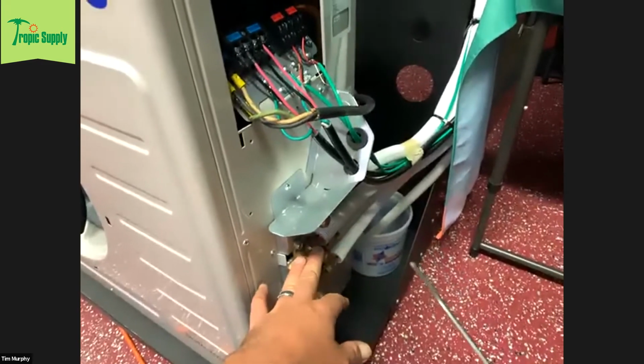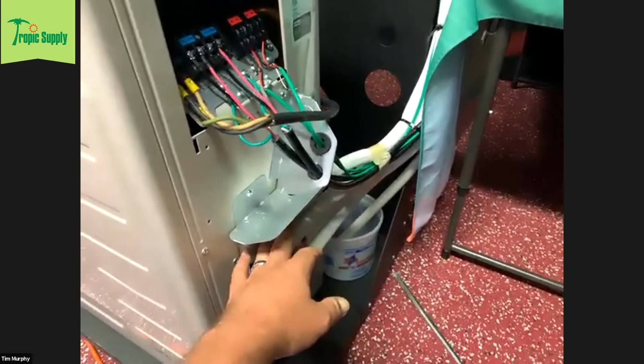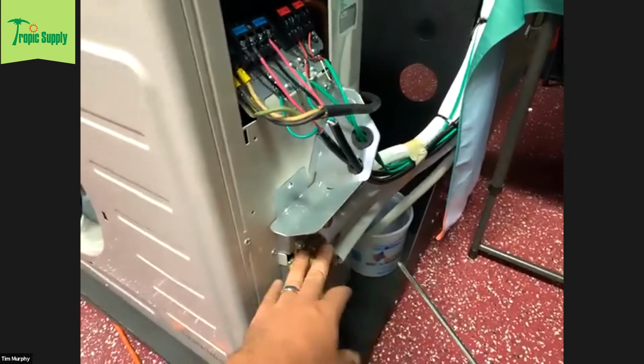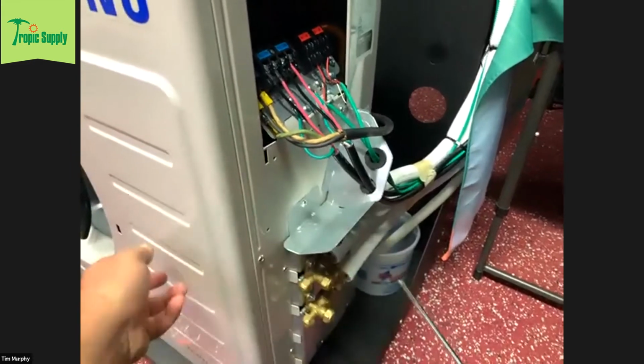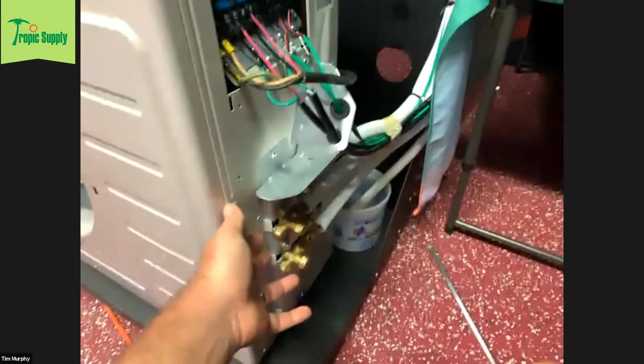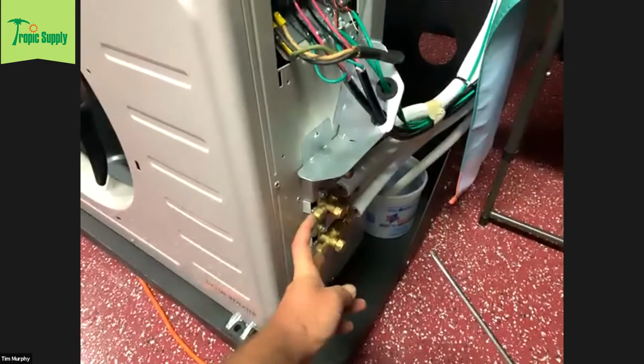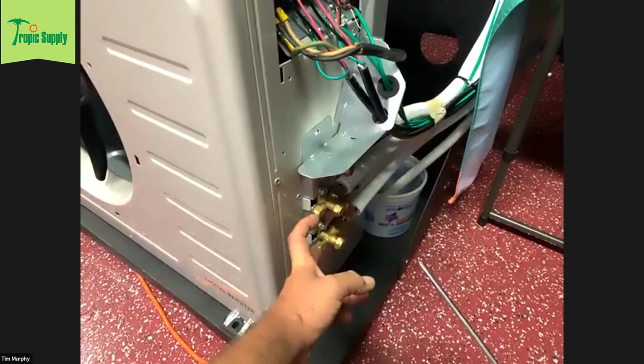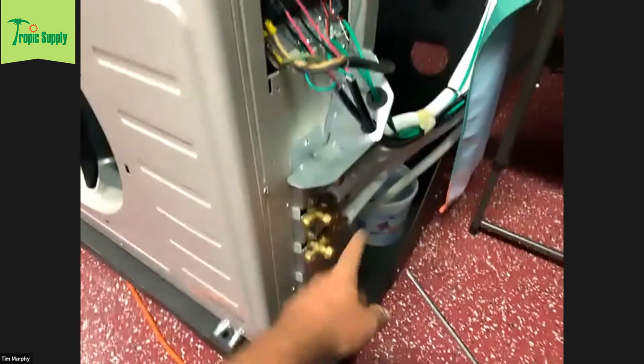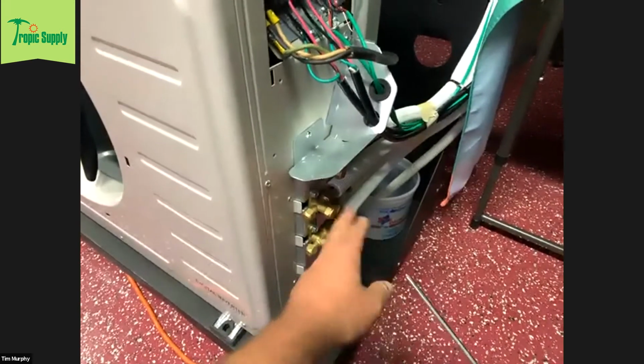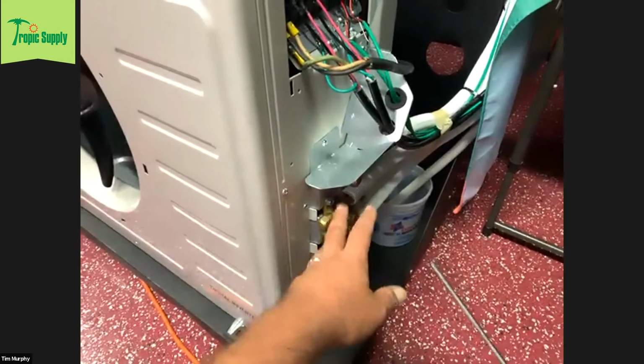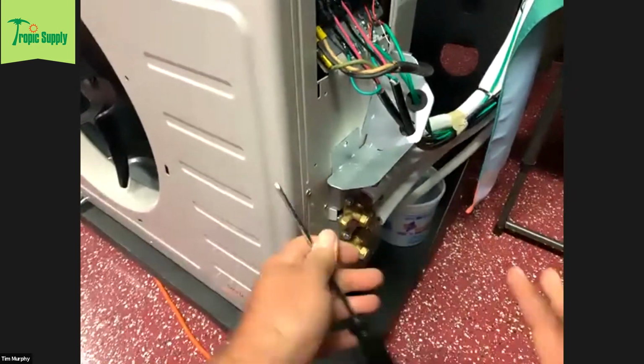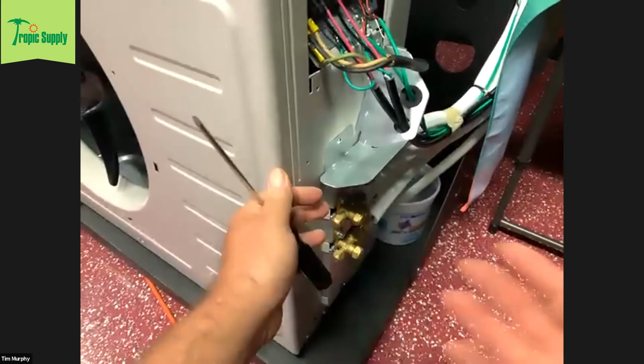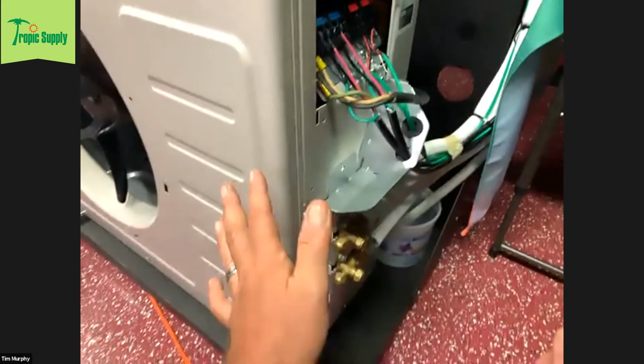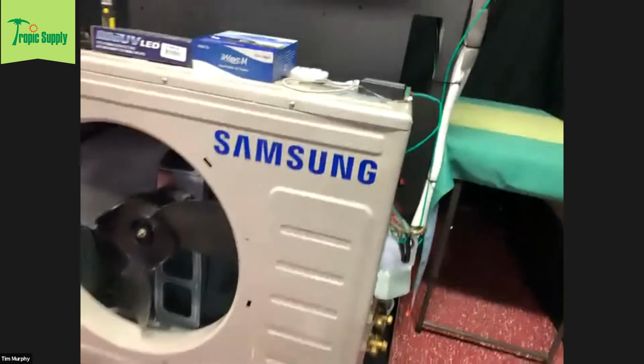You're just going to shut down the liquid line side of the valves, and then allow the suction to draw all that freon back into the compressor. You could do it one at a time if you want. I typically will throw my gauges on. If I'm doing a multi-zone, I'll put my gauges on both of them, and you will have to pump them down individually. I'll close down the high side valves on these and let it close all the way down. Once it pumps down almost to zero, I don't recommend going into zero, but just before zero, maybe 5 to 10 psi, shut the system down and close the suction, just like a typical residential system.